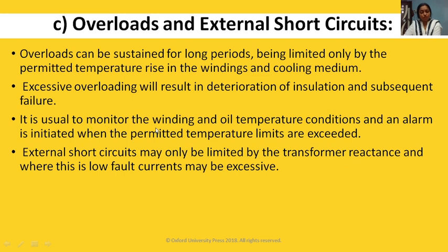It is usual to monitor the winding and oil temperature condition, and an alarm is initiated when the permitted temperature limits are exceeded. External short circuit may only be limited by the transformer reactance, and where this is low, fault current may be excessive.